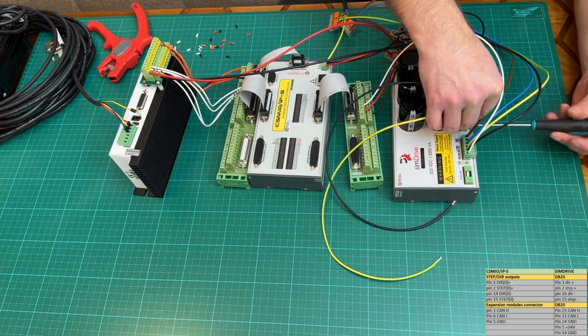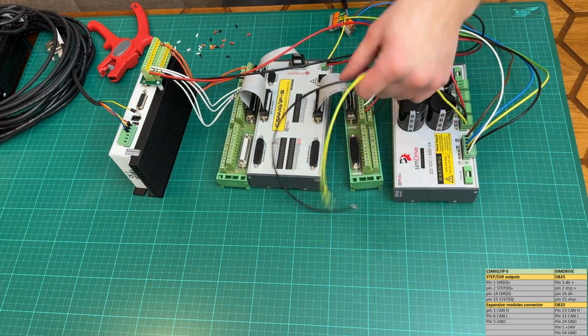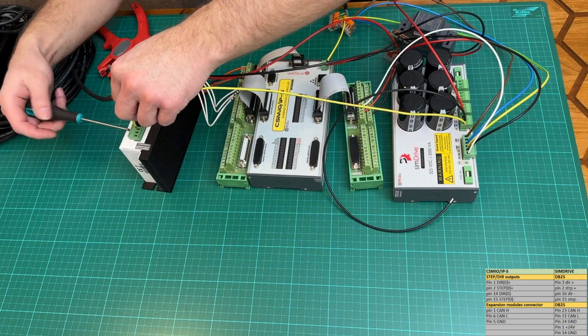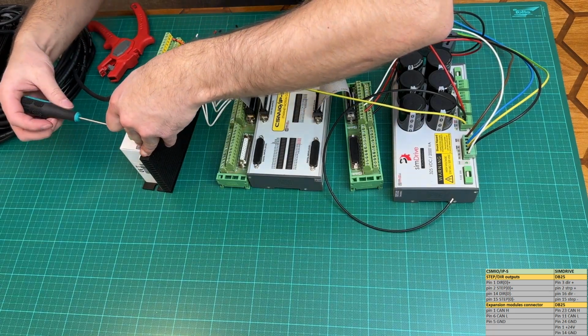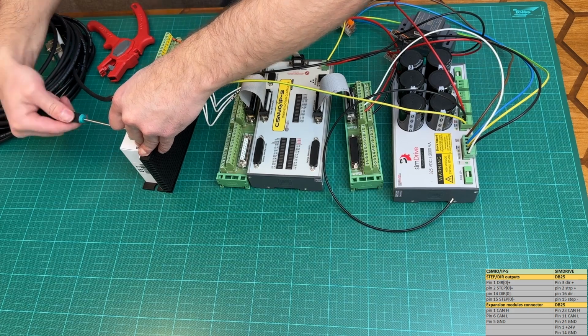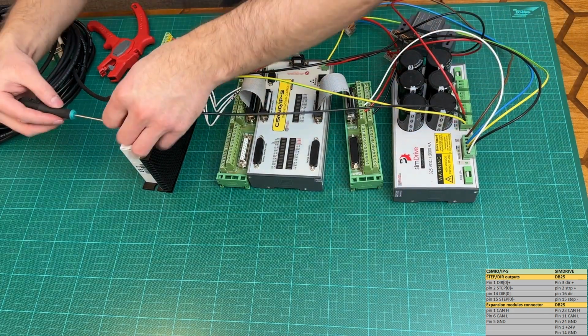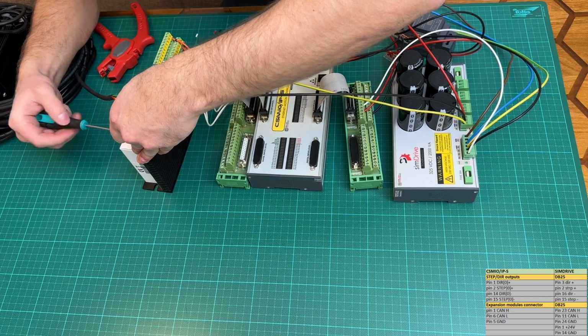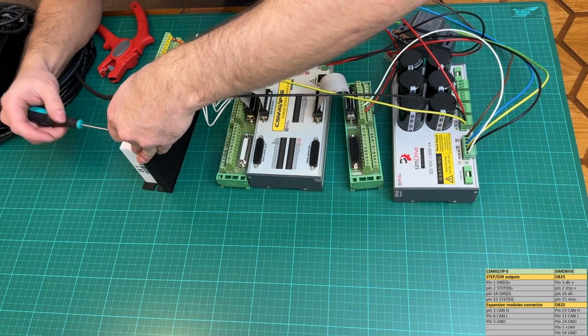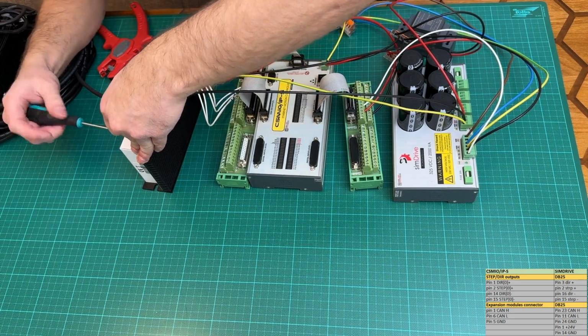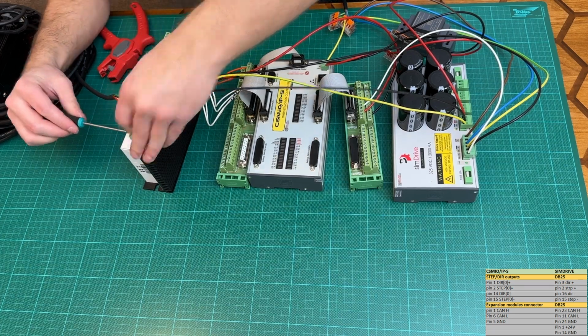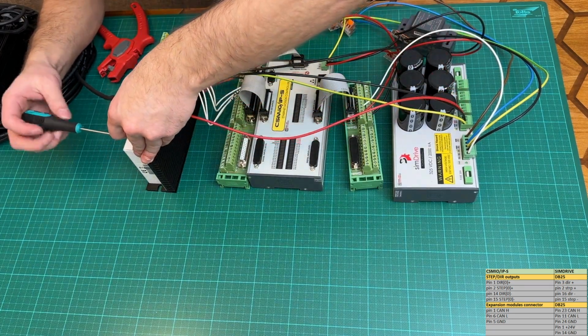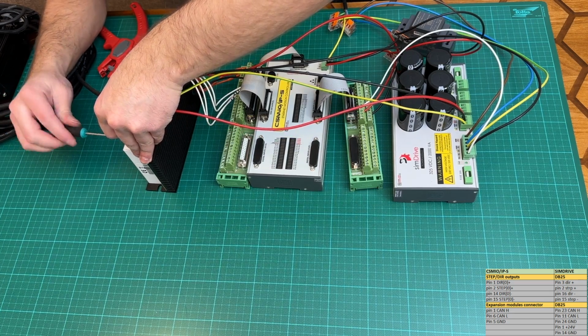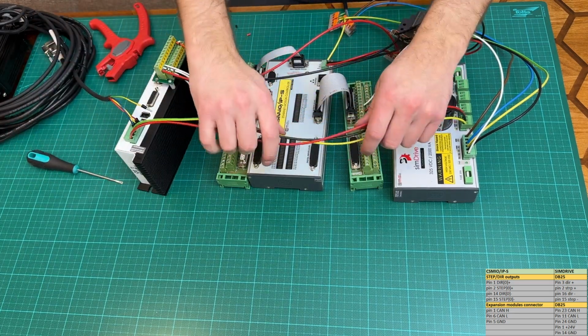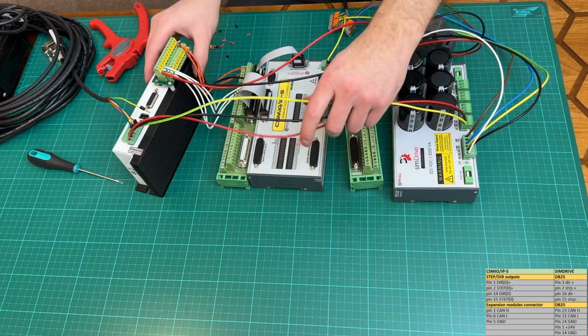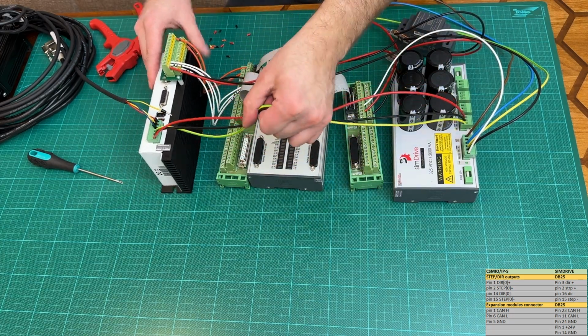When I read the power supply documentation, I found some interesting things. A power module has another cool function, namely, using a common power supply for many motor drives allows for recovering significant amounts of electrical energy, and also the power supply is not that loaded. It's because braking a servo motor works like an electric generator. The electric energy generated during braking is immediately used by other servo motors. If the energy wasn't used at once, it's stored in capacitors for later use.